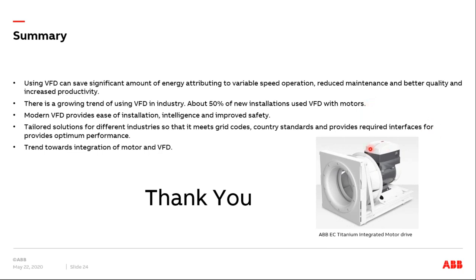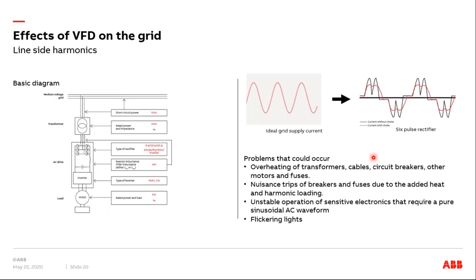Okay. Yes. So as I talked about in this slide, most of these VFDs have a six pulse rectifier, and the six pulse rectifier, you can see, has a lot of harmonics. I'm talking about the problem of overheating. I think from the grid side, the main impact would be overheating of your transformers and cables. So that would be one of the main problems that can be created because of the VFD connection if you don't have the right mitigation.